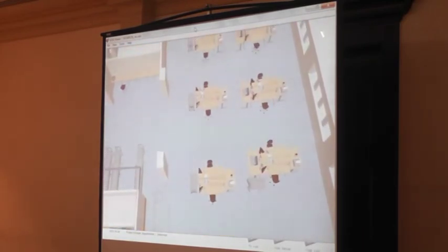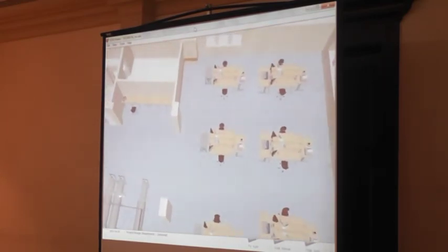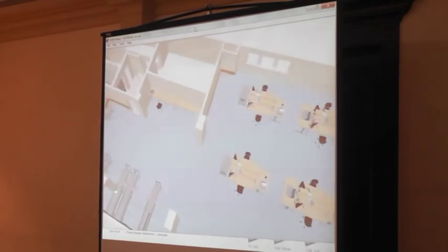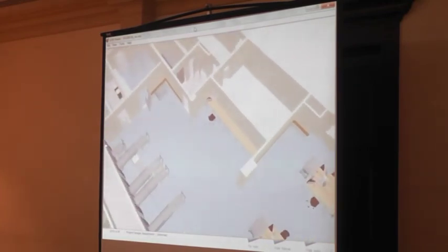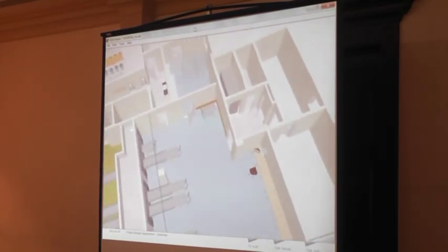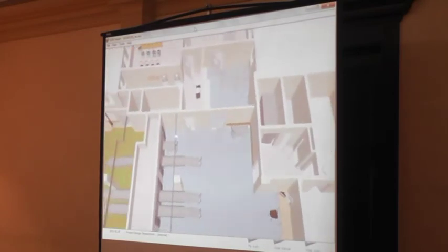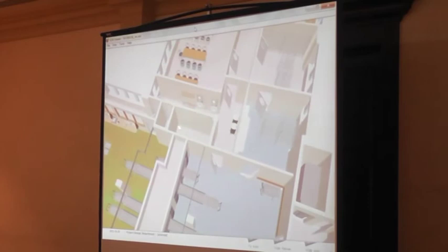The packing area with windows, as we discussed, and automatic loaders to the sterilizer, together with the low temperature sterilizers over in the top here. That is actually made shorter than the other low temperature sterilizer. This is with formaldehyde in this case. And here is the vacuum pump moved out in that room.